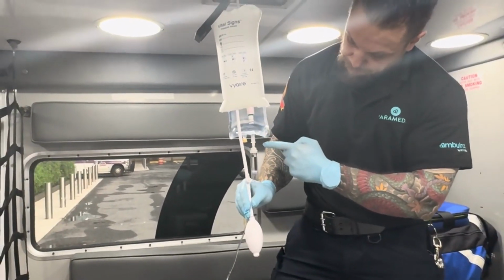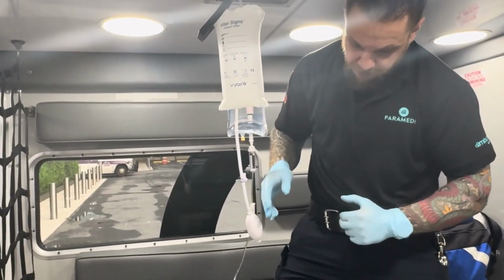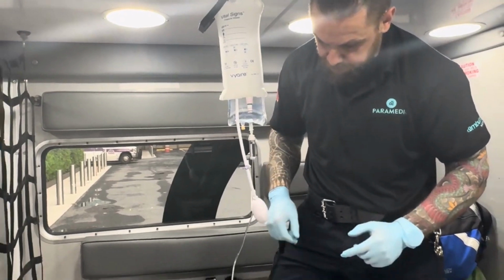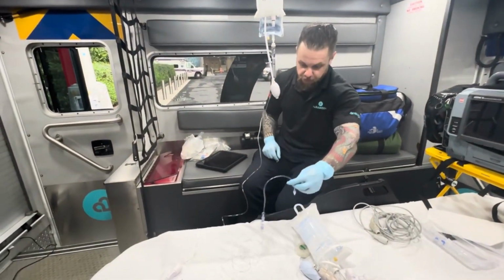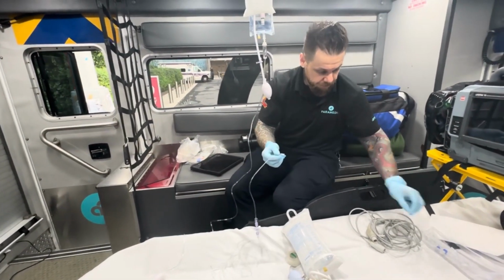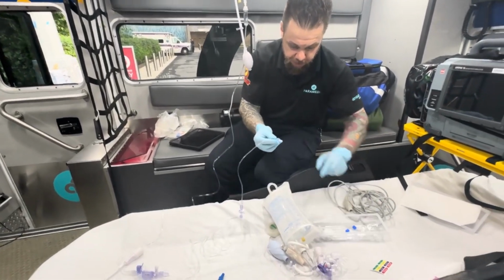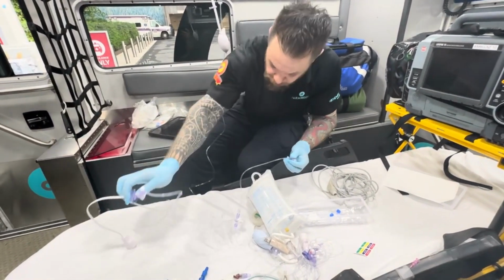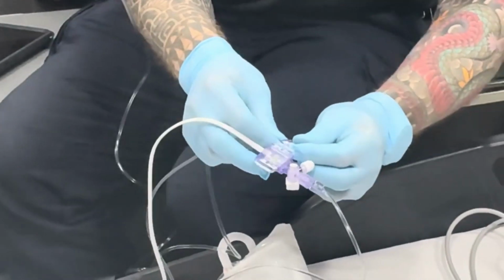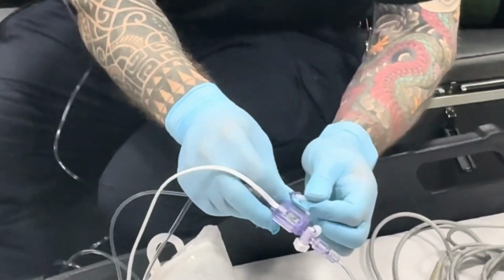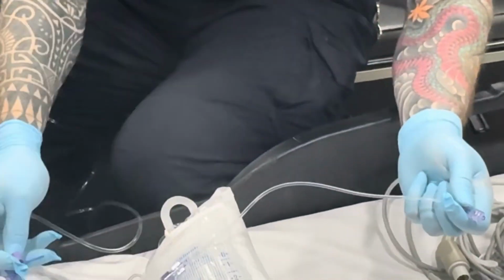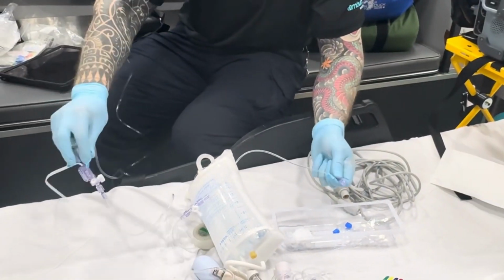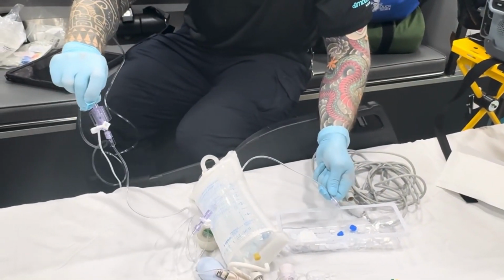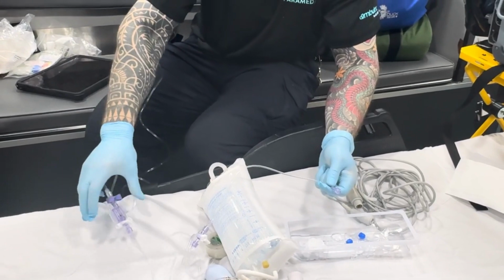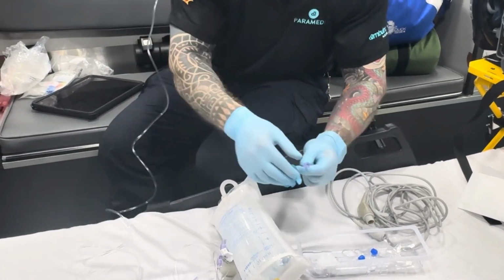This is what you're gonna do, right? So now we pressurize the system. How do you know you did it right? If I pull on this pigtail, right, you should have normal saline coming out under pressure, so it's going to be high pressure. So let me take this off, remove the cap, and I pull on this pigtail on the transducer. Right, you see how it comes out? So we did this correctly. I'm just going to replace the cap here.